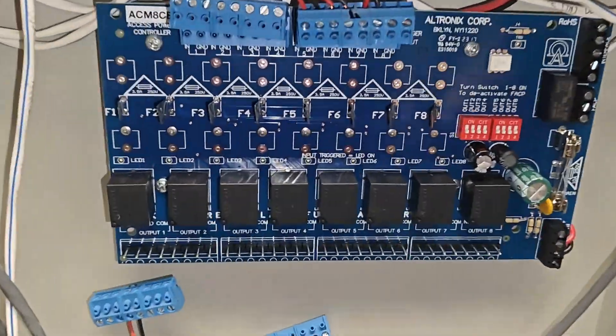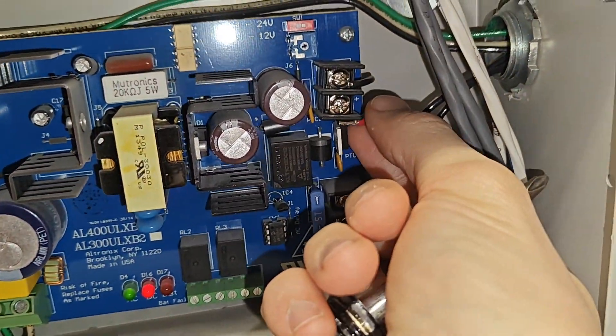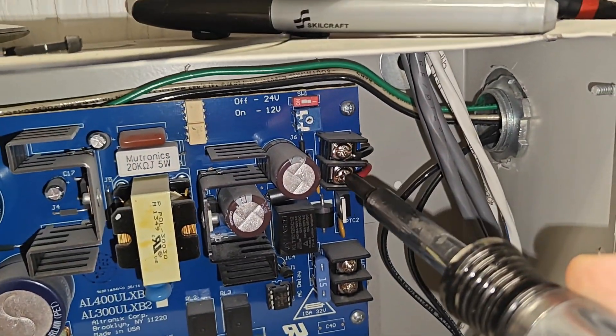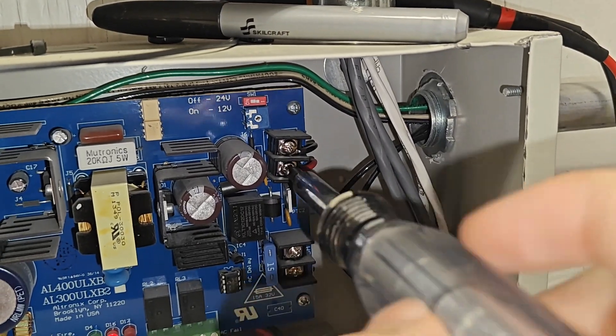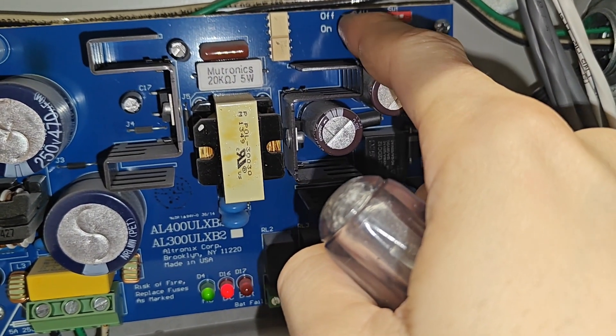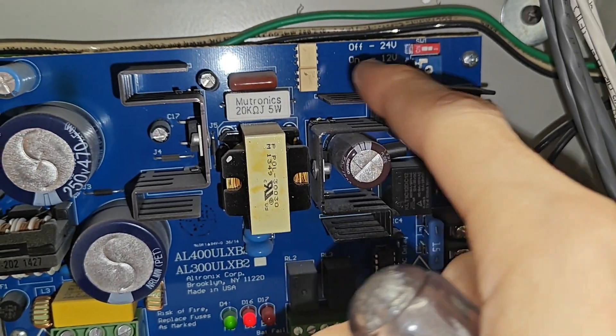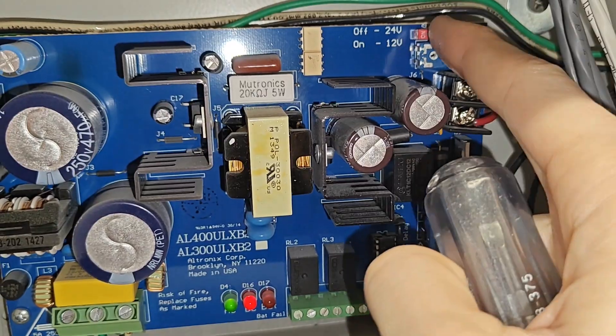I've got the new board installed. We'll just reconnect the power leg and tighten it up. We want to make sure our dip switch is set correctly — we want it to be 24 volts, so that's in the off position. For 12 volts that would have been on, so you always want to just double check that.